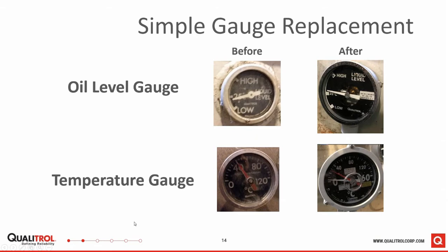There we go. And so for a little bit closer pictures of actual installations, typically on vault transformers, your liquid level gauge is a 3-inch gauge. And so before, if you notice at about the 8 o'clock or 8:30 position and 2:30 position, there are 2 screws on that gauge. You simply remove those 2 screws. You pull the existing liquid level gauge out. Despite what you might think, typically when pulling the liquid level gauge off, there's no oil that comes out. It's simply a magnetic gauge, and all the oil stays in the transformer.